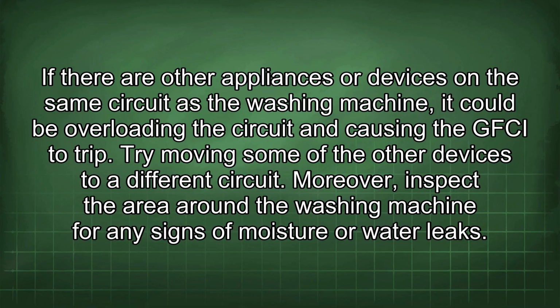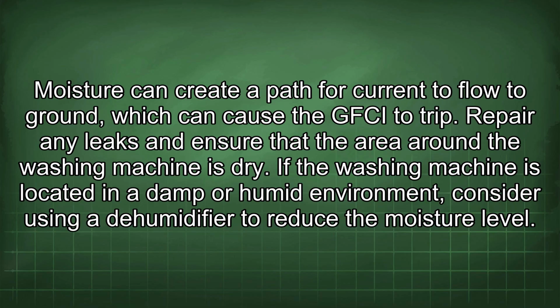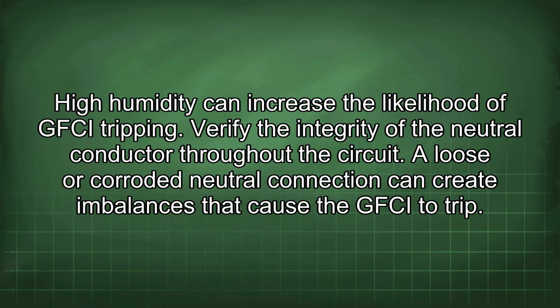Moreover, inspect the area around the washing machine for any signs of moisture or water leaks. Moisture can create a path for current to flow to ground, which can cause the GFCI to trip. Repair any leaks and ensure that the area around the washing machine is dry. If the washing machine is located in a damp or humid environment, consider using a dehumidifier to reduce the moisture level. High humidity can increase the likelihood of GFCI tripping.